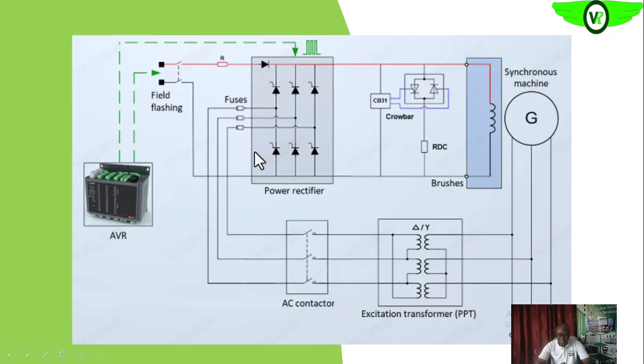So this is the schematic of the static excitation system. This is the generator, this is the output of the generator, and this is the excitation transformer that we saw earlier. That excitation transformer feeds the static excitation system. You see it on the power rectifier. The rate at which you fire these gates will determine what will be available to be sent to the main field by slip rings and brushes. Are we getting it? So this is the schematic.